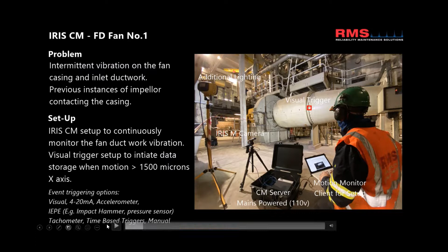That's what this case study is about. This is one of those 'bump in the night' situations, but we have people using it on critical assets 24/7, or in test cells remotely in another room. This was a bump in the night problem that only occurred once every two weeks. It was the fan impeller making contact with the casing, but only under certain load conditions.